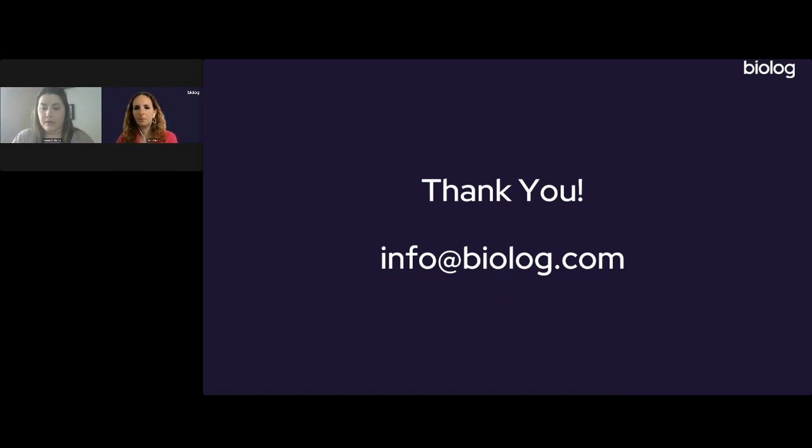All right. Our first question is, does Odin require an internet connection to do microbial identification? Hi, thanks for the question. No, actually. So with Odin, I mentioned this large database that we have, and it's actually locally stored on the instrument computer. And so you don't need to be connected to the internet. When you measure one of the ID plates, Odin's just searching the database that's local, and it can make a match. So if you have restrictions around connecting to the internet, no, you don't need an internet connection.